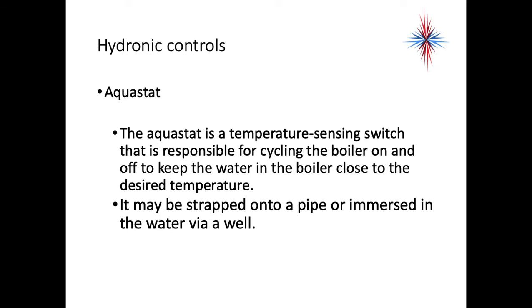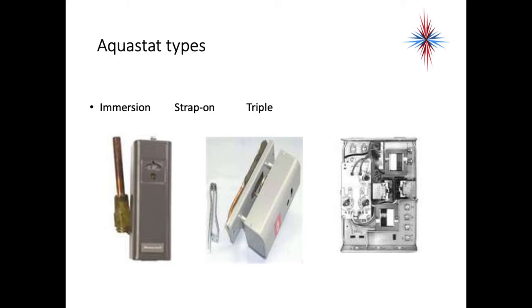The next component is the Aquastat. The Aquastat is a temperature-sensing switch responsible for cycling the boiler on and off to keep the water close to the desired temperature. It can be strapped onto a pipe or immersed in the water via a well or access point on the boiler. There are several types: an immersion type that screws into the boiler, a strap-on type that clamps onto a pipe, and a triple Aquastat, which is by far the most frequently found due to its functionality.